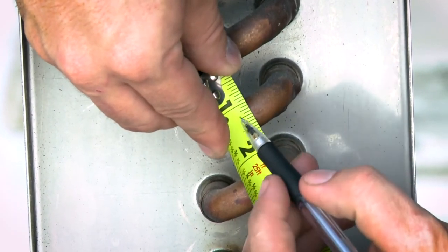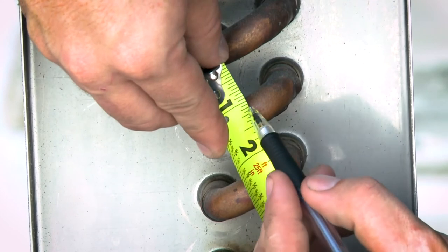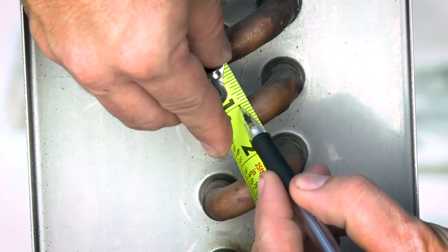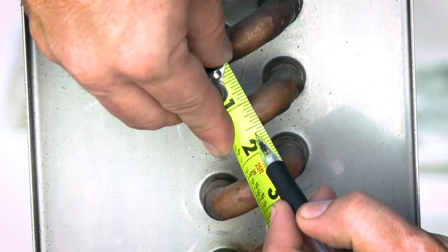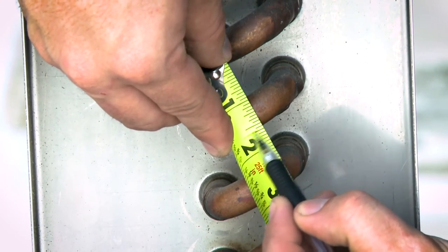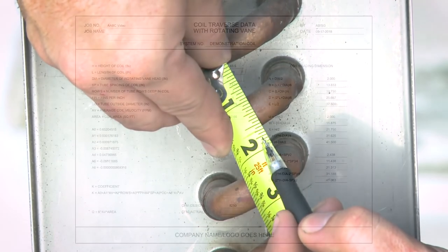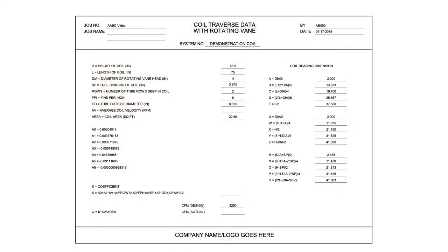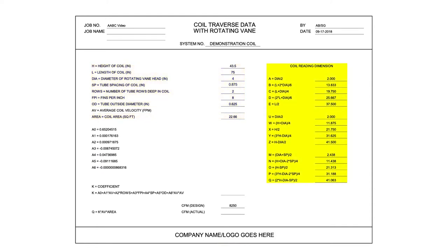Measure the coil's tube outside diameter and verify that the measurement matches the submittal data on the form, which is indicated at 0.625 inches. The recorded and verified values for H, L, DIA, SP, ROWS, FPI, and OD completes the data required to automatically calculate the coil reading dimensions.